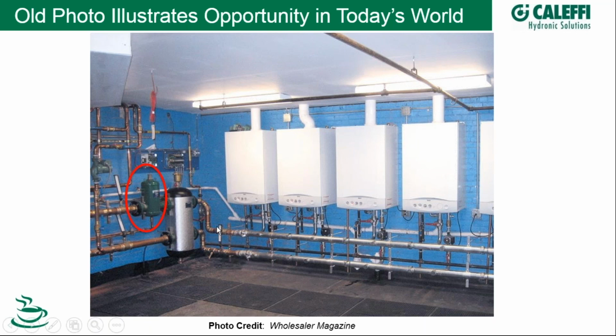So the question is, I think, if you have a domestic hot water call and you don't have any heat demand, could you create ghost flow, which I think he's referring to? Would these pumps, let's say we just have a one boiler system, with no demand, would you inject flow into your secondary because you want to satisfy getting flow out to your indirect hot water heater? And the answer to that is no.